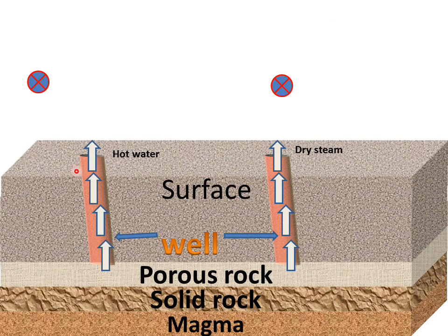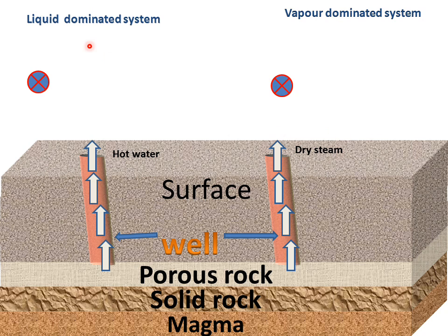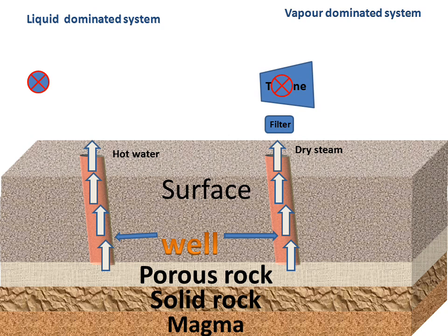We have the surface with a well drilled down to the porous rock. This is a vapor-dominated system in which we use dry steam. This is a liquid-dominated system in which we use hot water or a mixture of steam and hot water. In the vapor-dominated system, there will be a filter for filtering the dry steam — impurities and any metal particles will be filtered at this step. Then there will be a turbine, and this filtered steam will reach the turbine for rotating it.